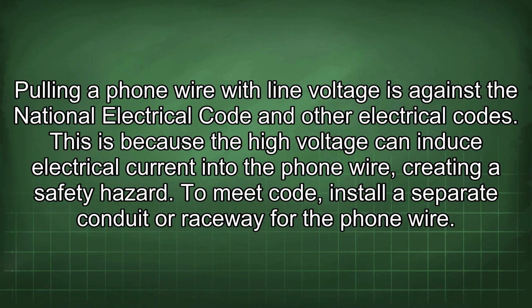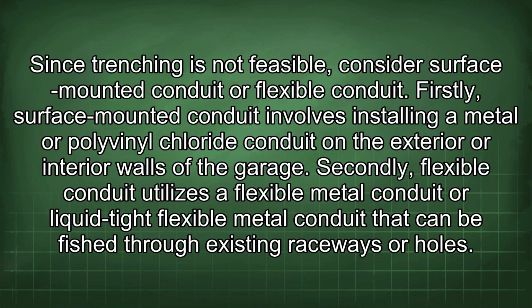Pulling a phone wire with line voltage is against the National Electrical Code and other electrical codes. This is because the high voltage can induce electrical current into the phone wire, creating a safety hazard. To meet code, install a separate conduit or raceway for the phone wire. Since trenching is not feasible, consider surface-mounted conduit or flexible conduit.